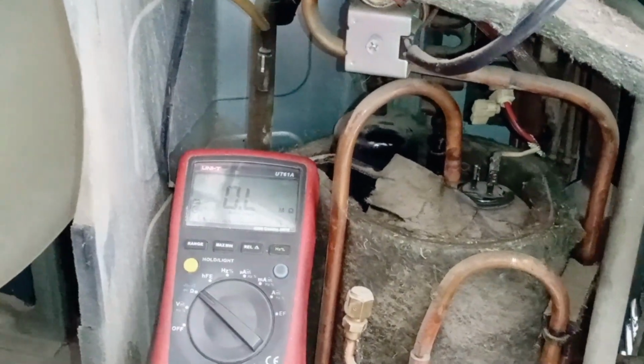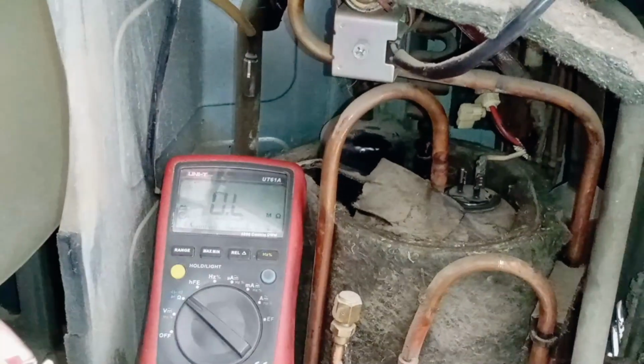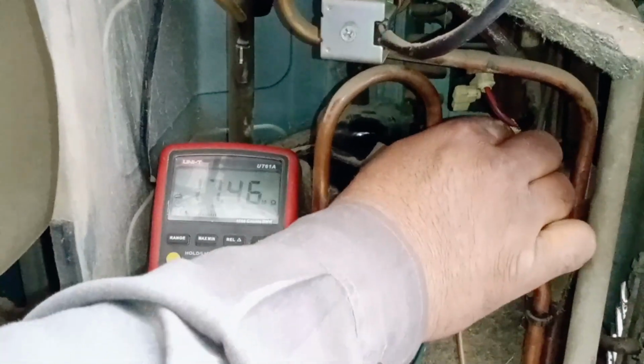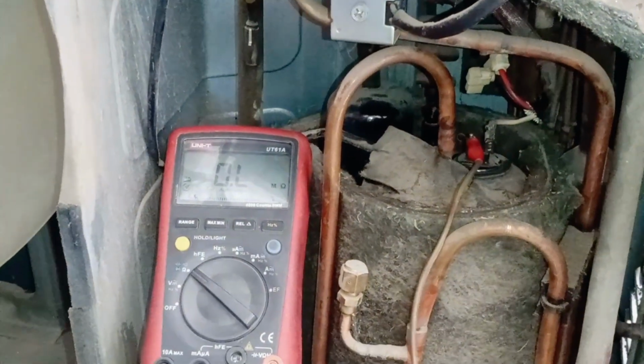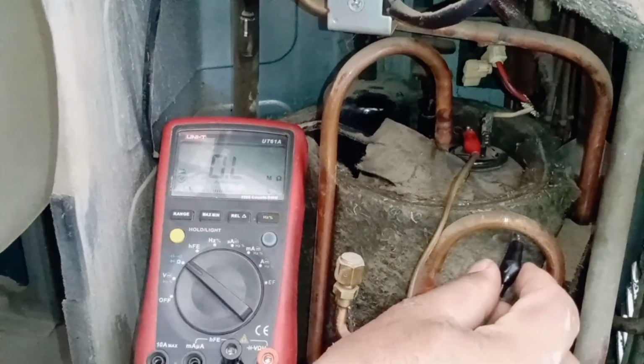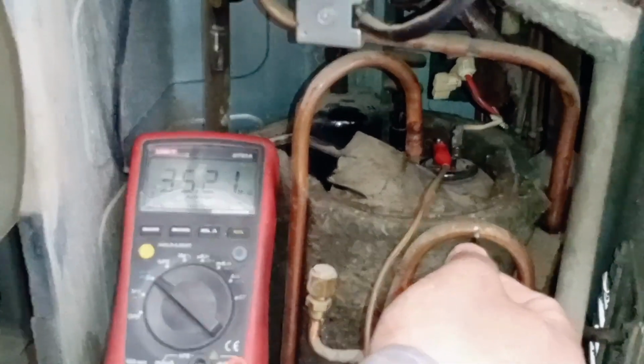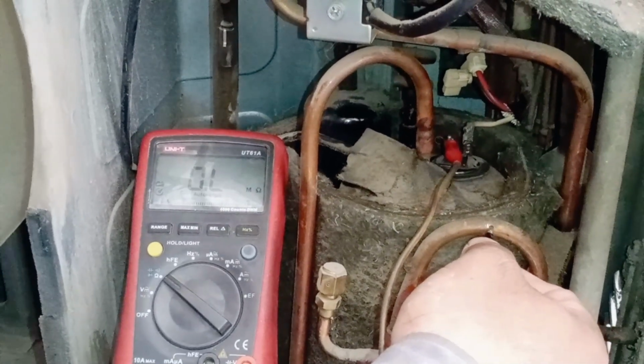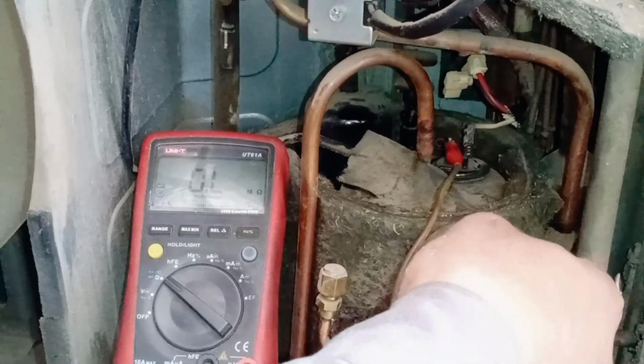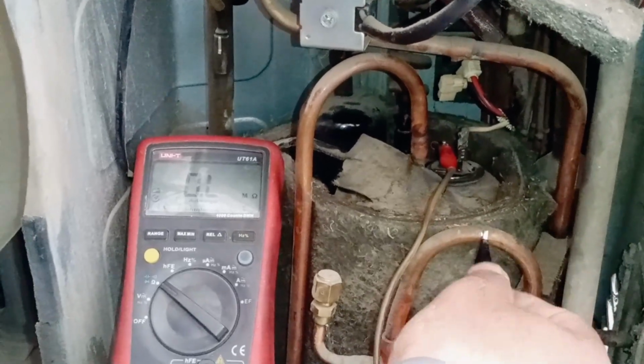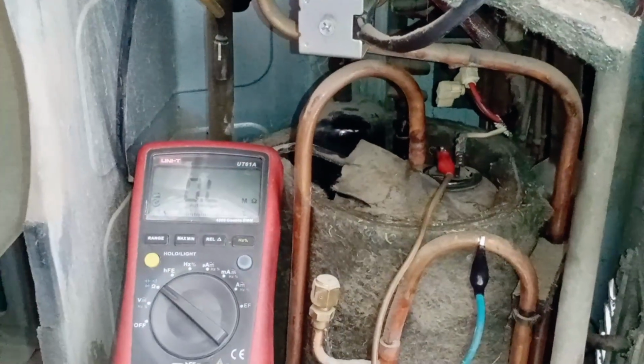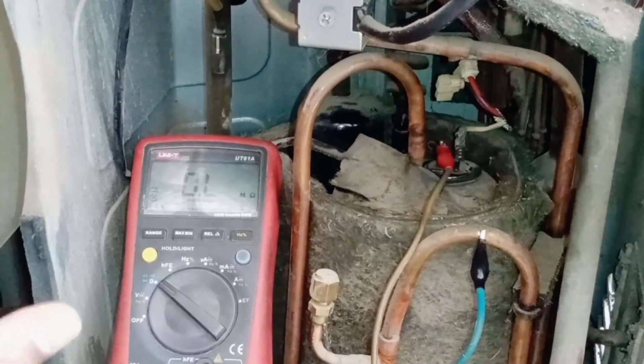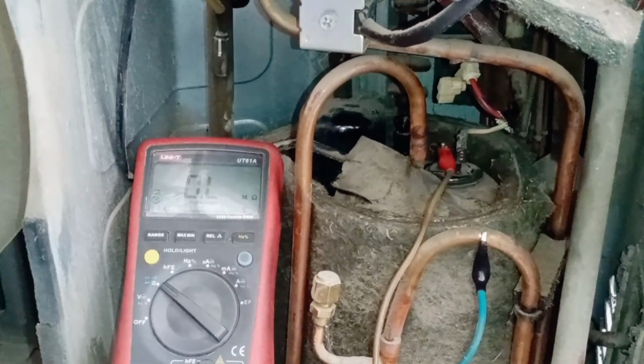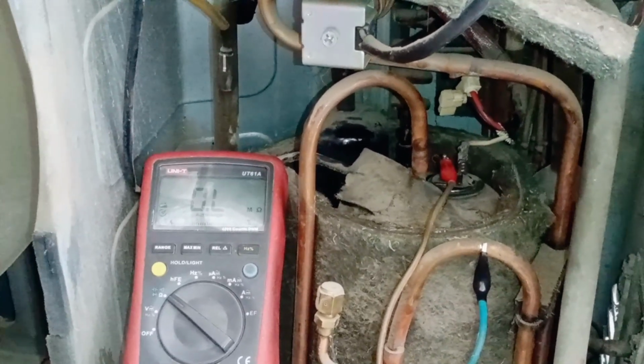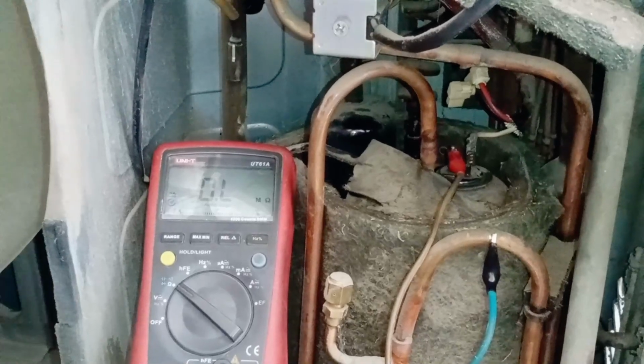Despite the circuit board being okay, the compressor still isn't working. I am reconnecting the red probe with the compressor terminal and the black probe with the copper pipe. It now shows approximately 30 megaohms and the value has disappeared. This compressor shows a leakage of approximately 40 megaohms, which is quite high. At this level, compressors typically work fine. However, this compressor isn't functioning properly. So make sure not to make this mistake yourself and avoid any potential damage.